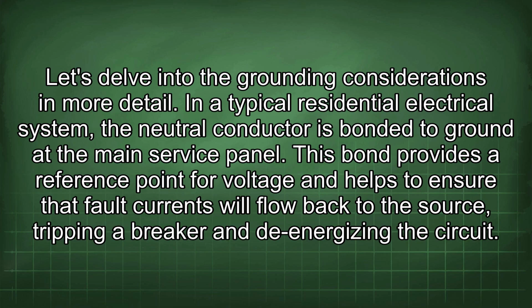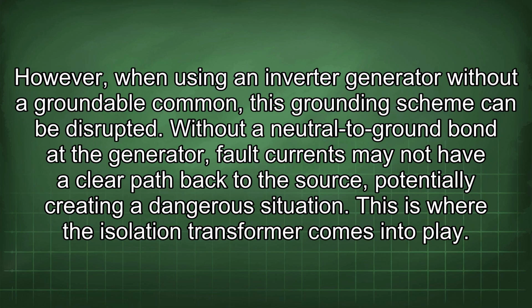In a typical residential electrical system, the neutral conductor is bonded to ground at the main service panel. This bond provides a reference point for voltage and helps to ensure that fault currents will flow back to the source, tripping a breaker and de-energizing the circuit. However, when using an inverter generator without a groundable common, this grounding scheme can be disrupted.